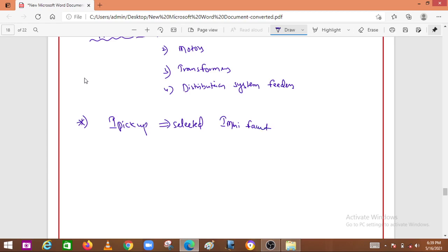Here, we have two types of systems, the distribution system and the transmission system. A three-phase fault with maximum generation gives the maximum value of the fault current, but in the transmission system an LG fault with minimum generation gives the minimum value of the fault current, and in the distribution system a line to line fault with minimum generation gives the minimum value of the fault current.